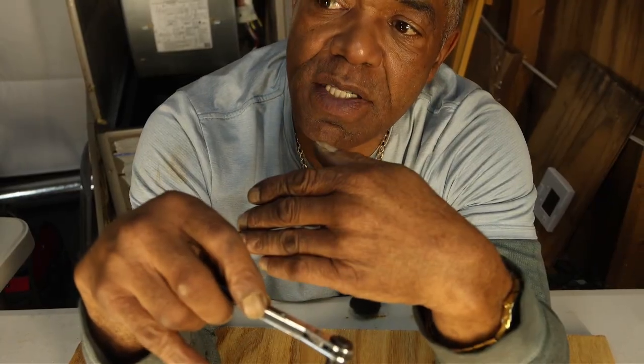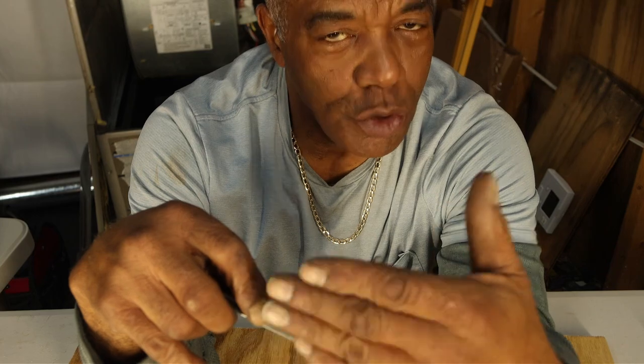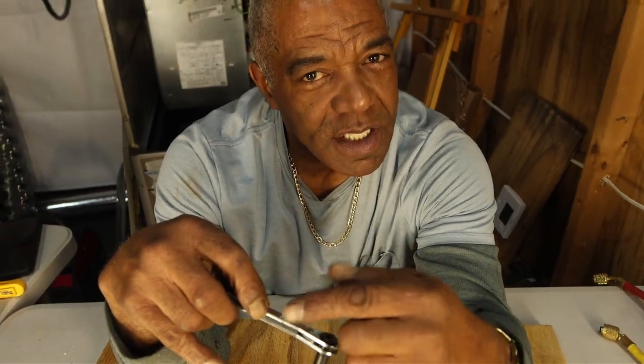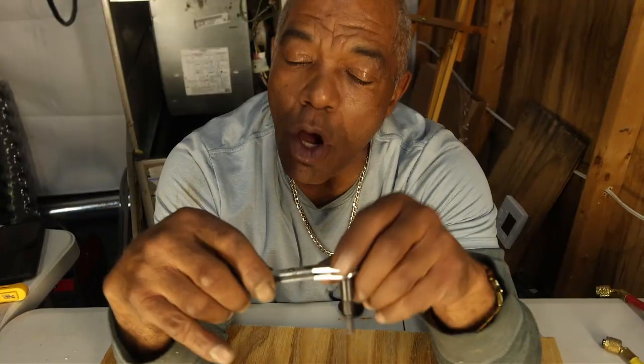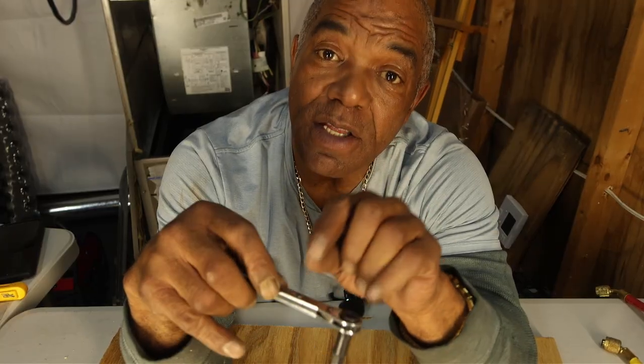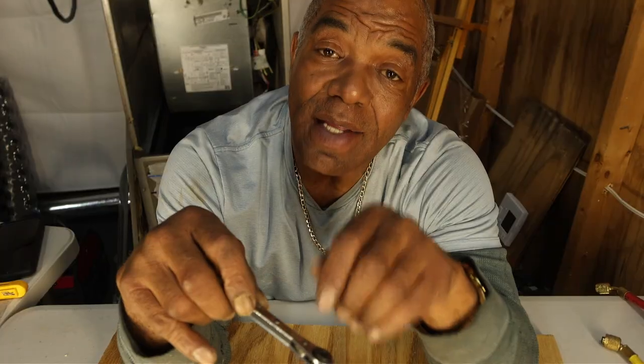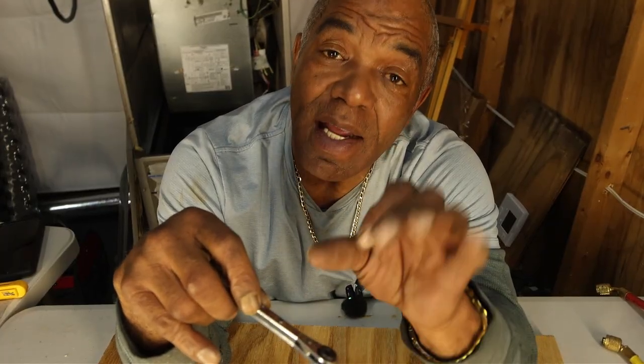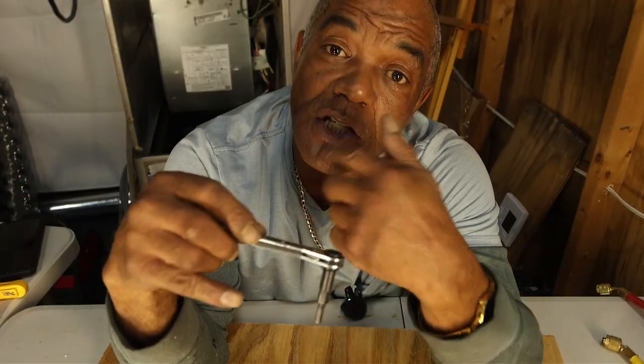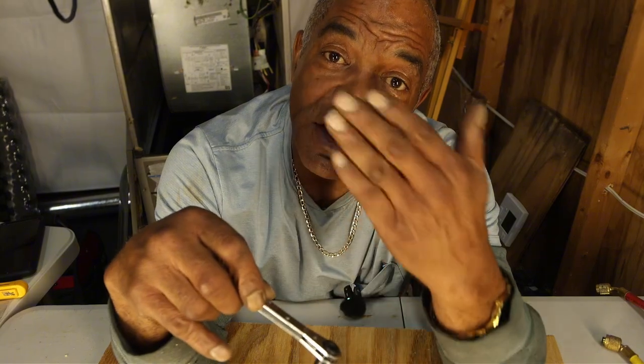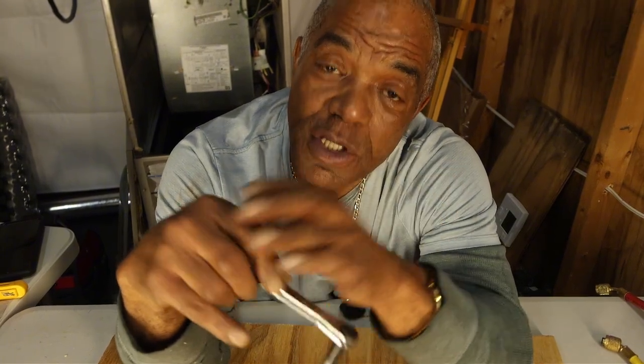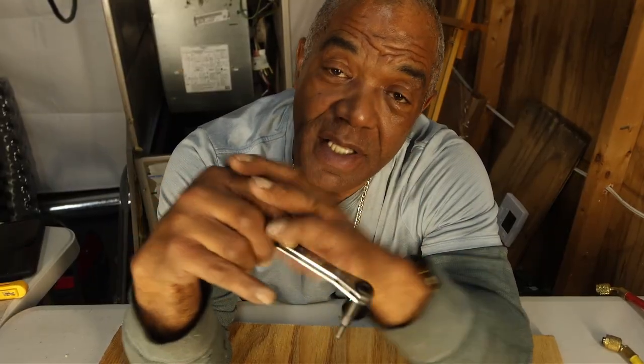I'm going to repeat these things over and over all throughout the class because you need to remember, you need to learn this, and we know it takes repetitively going over. So I'm going to continue to talk about the red is the high side. It's the smaller of the two coppers, and it is the non-insulated. That's the red side, that's the high side, that's the liquid side, that's the thinner of the two coppers. But the suction, that's the low side, that's the blue line, that's the thicker of the two coppers, and that line would always be insulated.